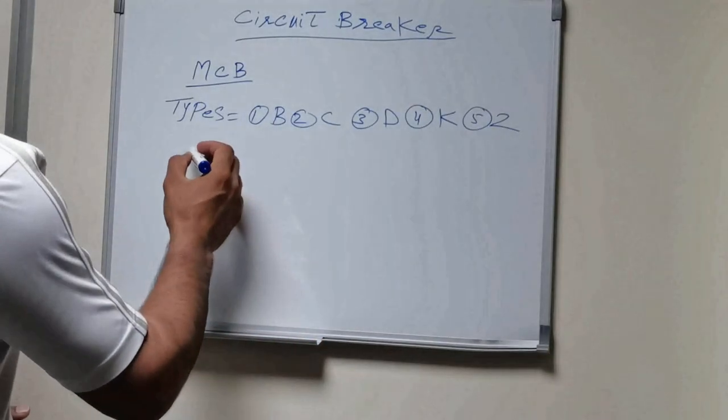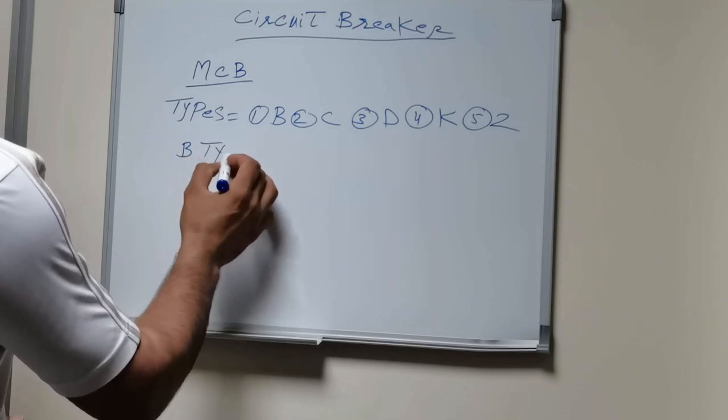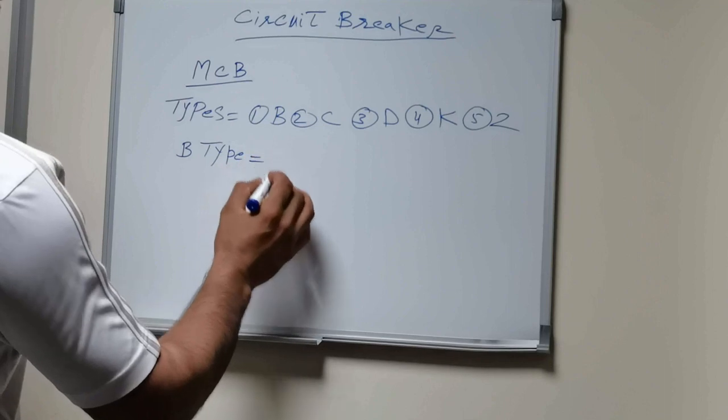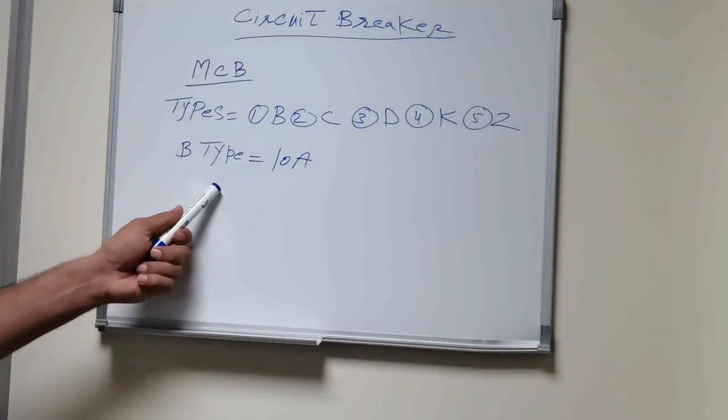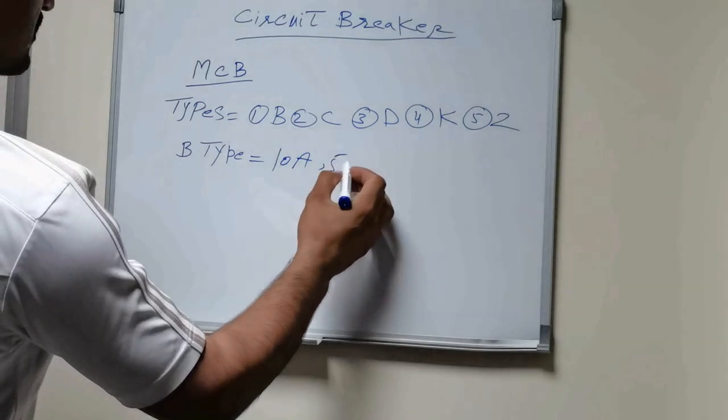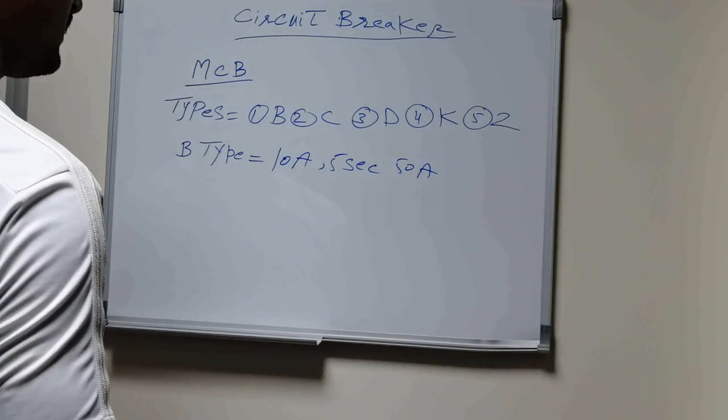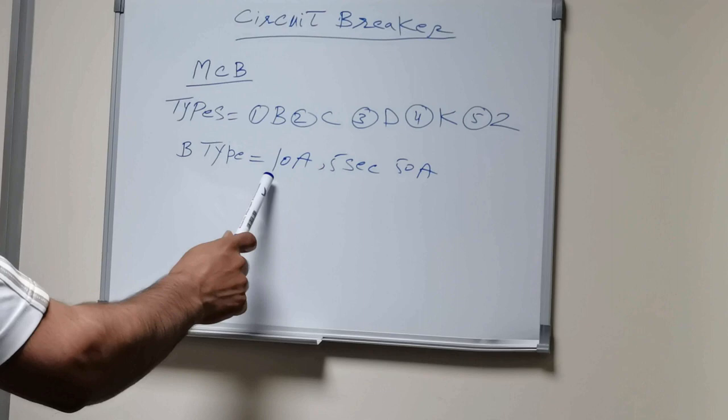For example, if we use MCB Type B, it means this breaker can stand up to 5 times of its current rating for 5 seconds. So it can stand up to 5 seconds for 50 amps. Within the 5 seconds, this breaker will trip if the load exceeds from 10 amps.